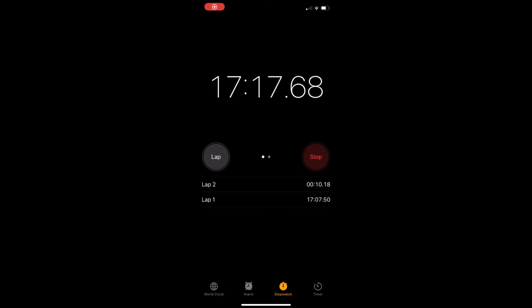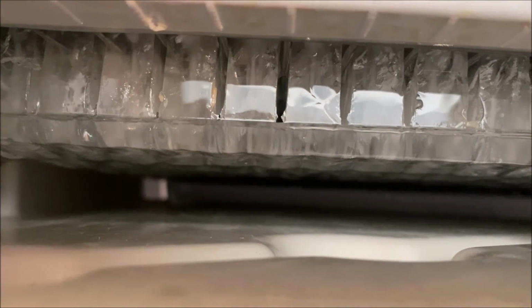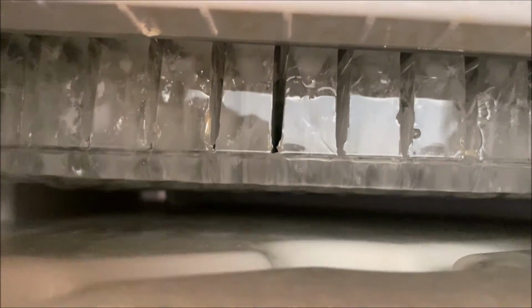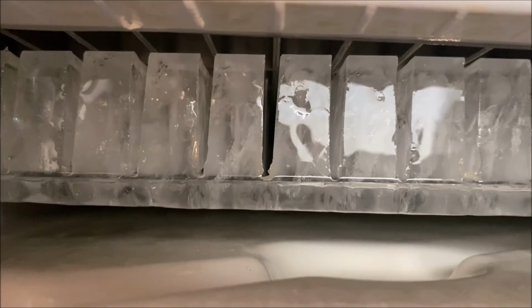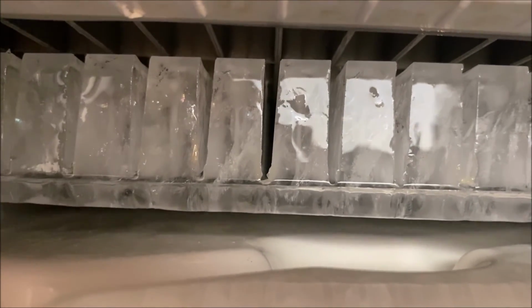And as always, we want to time our cycle. So our freeze cycle was 17 minutes, and you can see we're 15 seconds into our harvest cycle. And look at that, we're starting to drop ice off the coil. And look at the cubes, they're nice and uniform. Bridge thickness is great on this one. Our timing's really good. So we know we don't have a harvest issue.